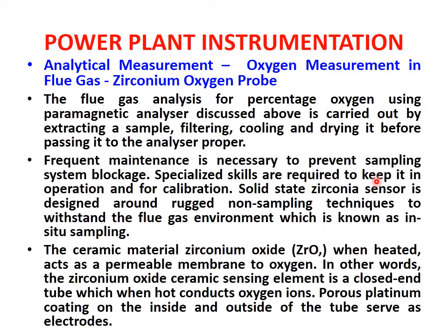So as we have seen, the maintenance required is more. Specialized skills are required to keep it in operation and for calibration. So the solid state zirconia sensor is designed around rugged non-sampling techniques to withstand the flue gas environment, which is known as in situ sampling.